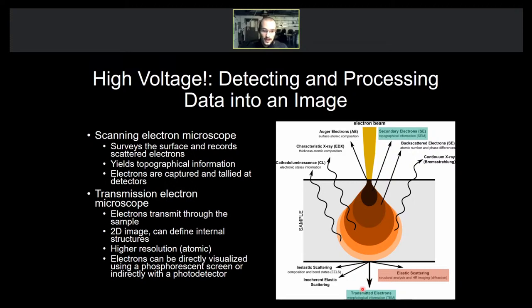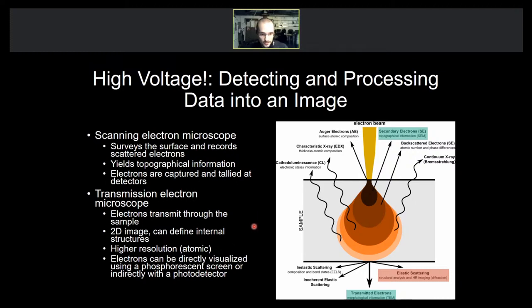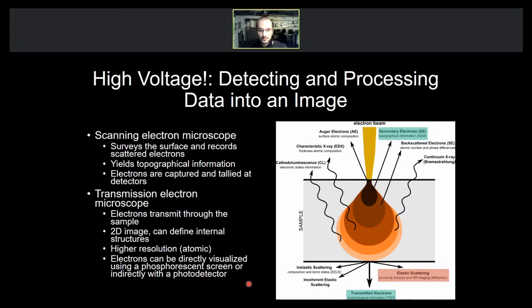Transmission electron microscopes let electrons go all the way through the sample, achieving atomic resolution. You can visualize the electron beam striking a phosphorescent screen to align and tune the microscope. Sample prep is a major consideration — you have very small sample volumes and must treat the sample appropriately to get high-resolution images. It's not as easy as an optical microscope where you just put a slide and look at it, but you can get very valuable information as a result.